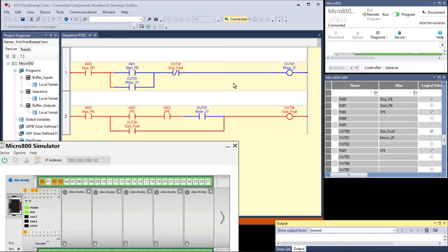Now, conveyors do have a little coast depending on the inertia of the belt and the rollers and the objects on the belt. So if you have all the stuff moving, then all of a sudden you turn the motor off, and you're not using a brake to stop it in place, which I don't think is necessary. I think you can adjust your photo eyes and speed so you don't coast out of photo eye one. And even if you did, so what?